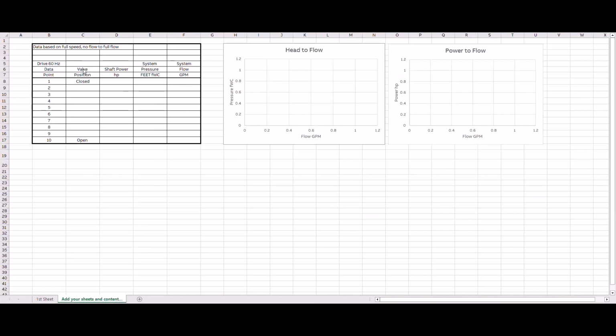In this Excel sheet, we have a simple chart set up for shaft horsepower, system pressure in feet of water column, and system flow in gallons per minute. Looking at this chart, we're going to fill out the chart, and we're going to look at our graphs for head to flow and our graphs of power to flow. Let's take a look at the information that we have. The first information for point 1 was at 0 flow, so let's enter it into the chart.